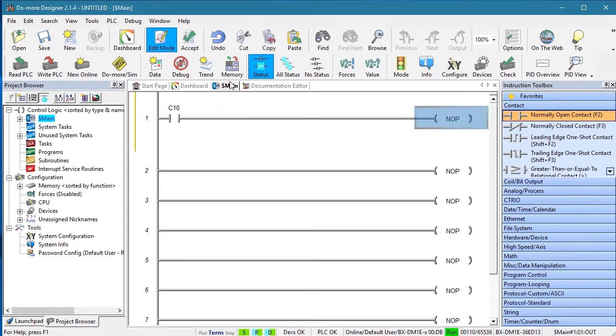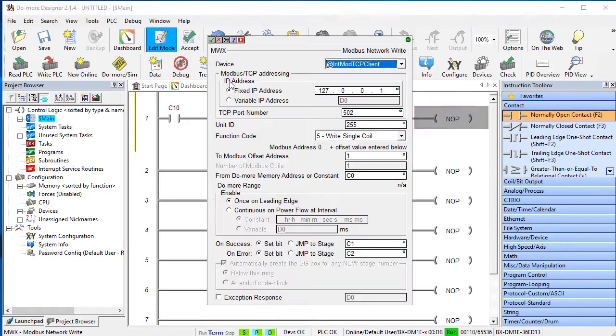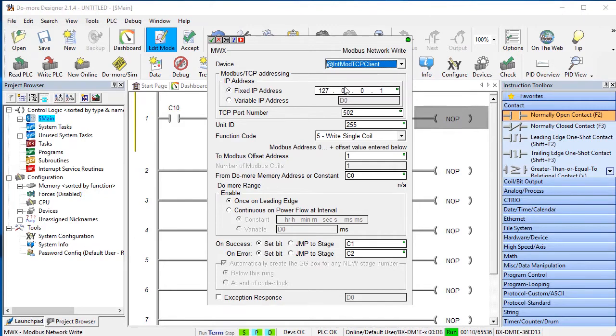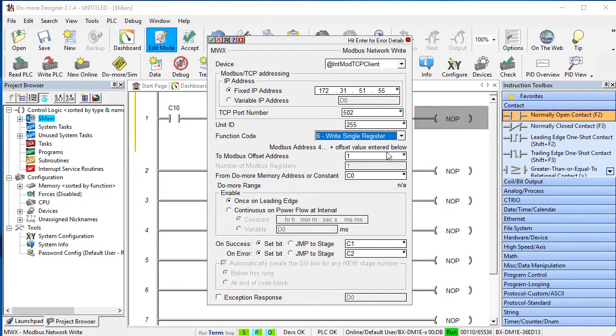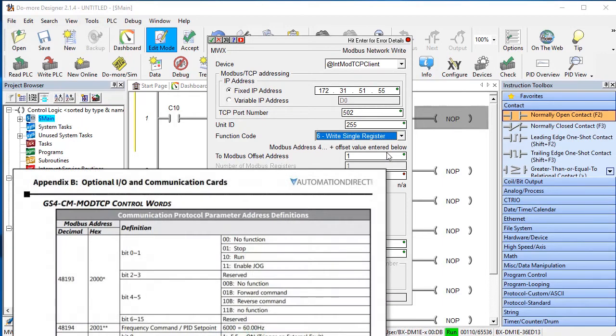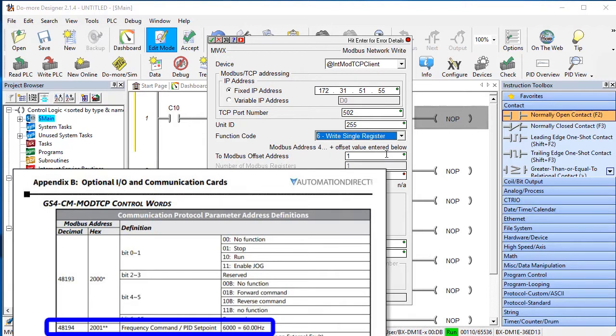Let's have C10 do a Modbus write. We need the built-in Modbus TCP client, our GS4 Drive is at this address, and we are writing to a single location. In Appendix B of the GS4 user manual we see that Modbus TCP frequency commands need to be sent to address 8194.